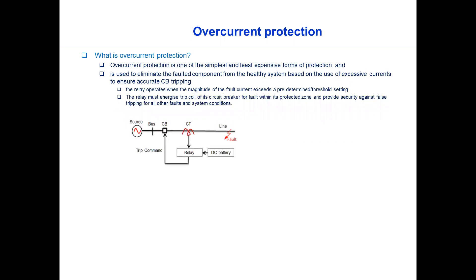This is the single line diagram of how the relay is coordinated in the system. So for example, this is the relay. The relay will take information through the CT or current transformer when there is a fault on the line, and then if the fault current or the information from the CT is higher than the pre-determined setting of the relay, then the relay will initiate a trip command to the circuit breaker and the circuit breaker will disconnect this network from the rest of the network.